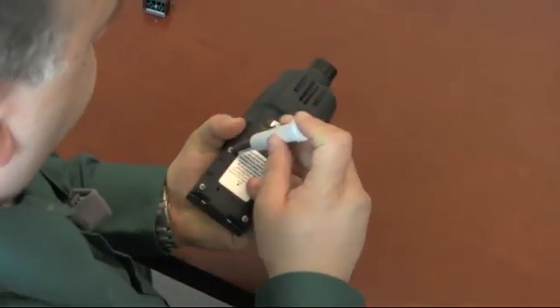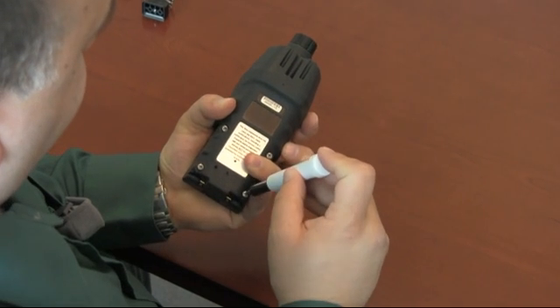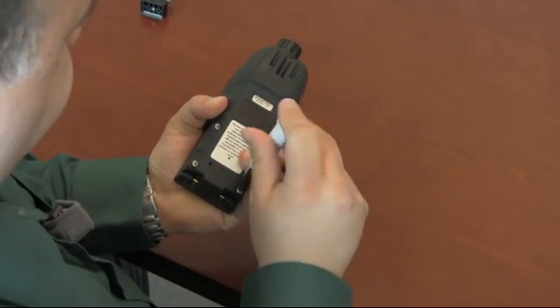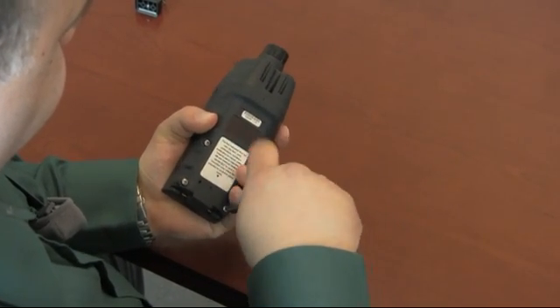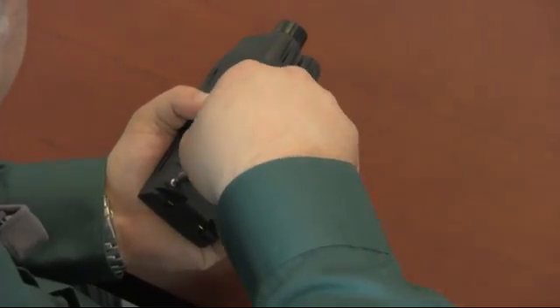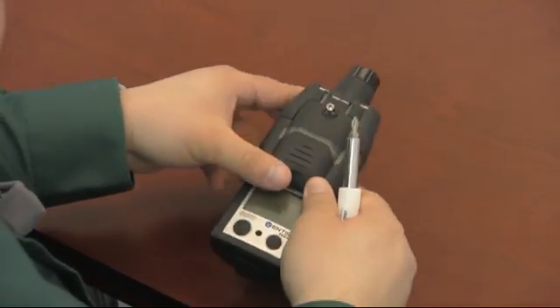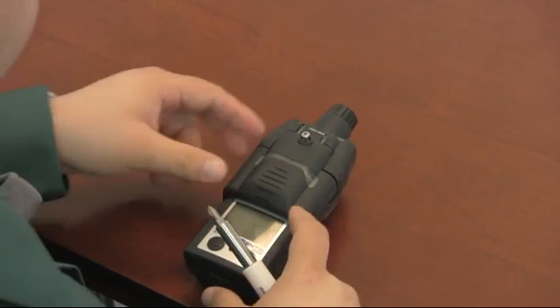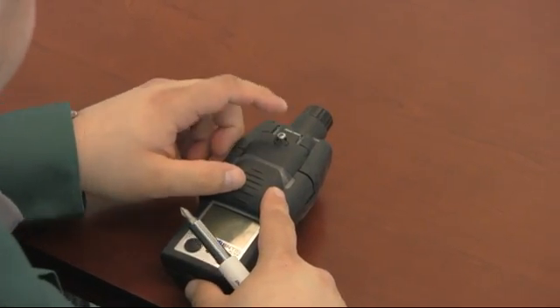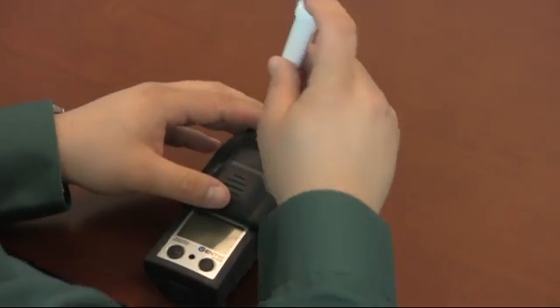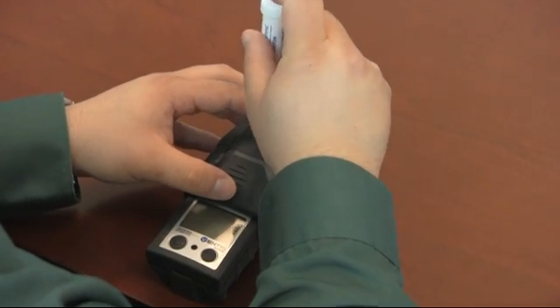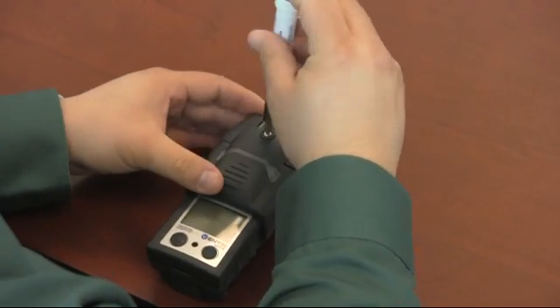Grab your screwdriver, and there's again four screws that you'll need to tighten up. Then there's one more screw on the pump door, and it's actually a spring-loaded screw. So we'll take our screwdriver, push down on it, tighten it up.